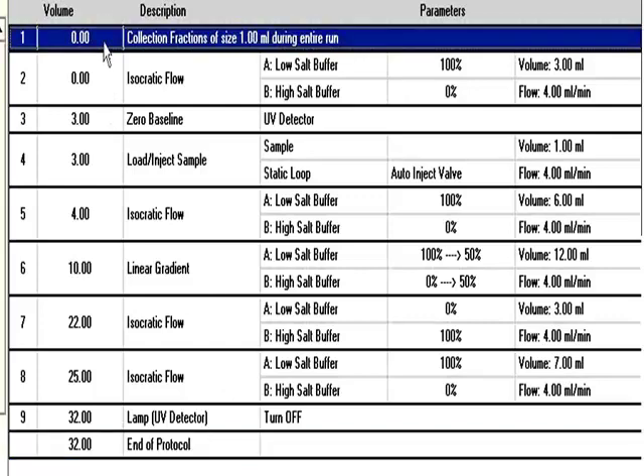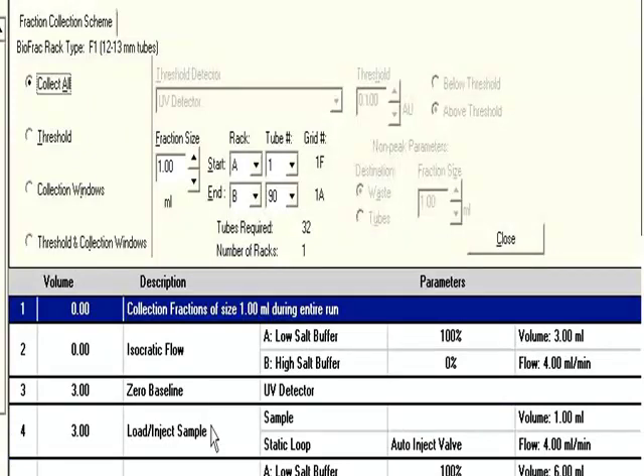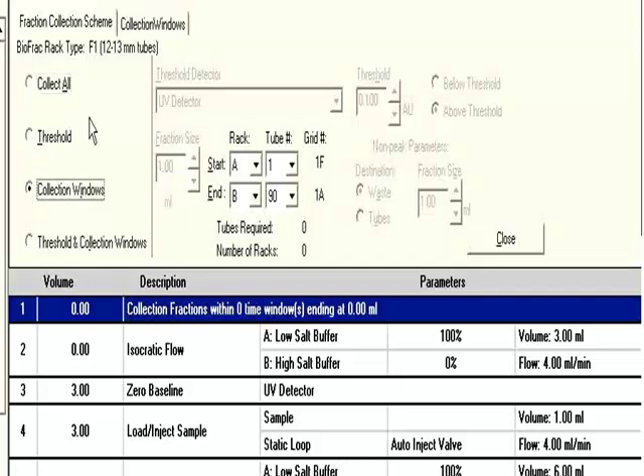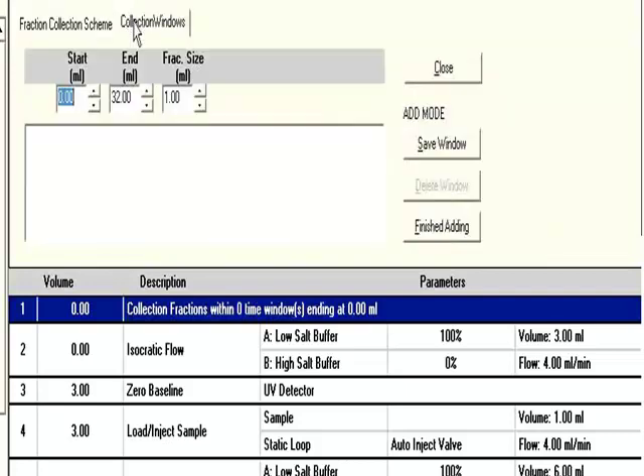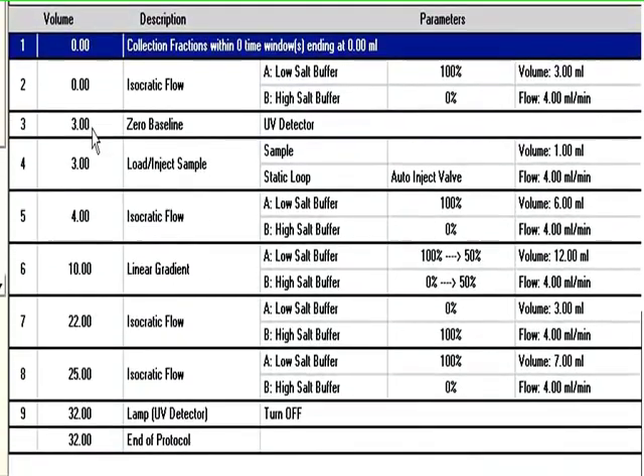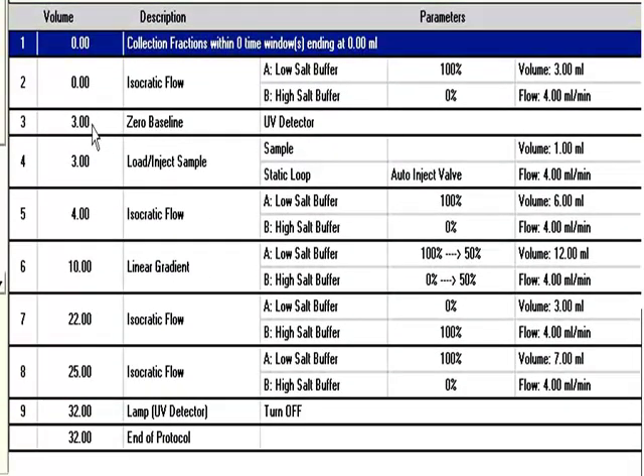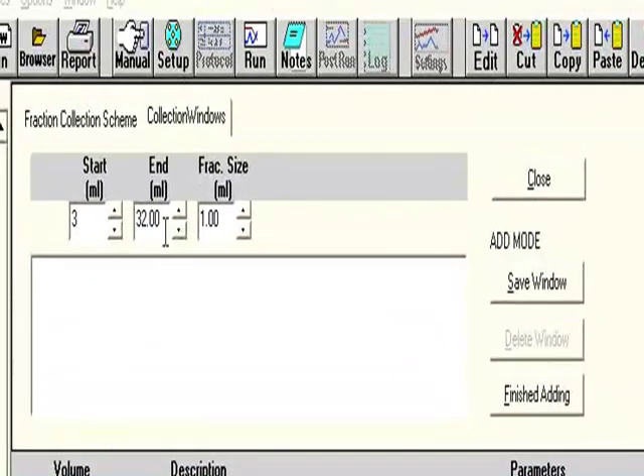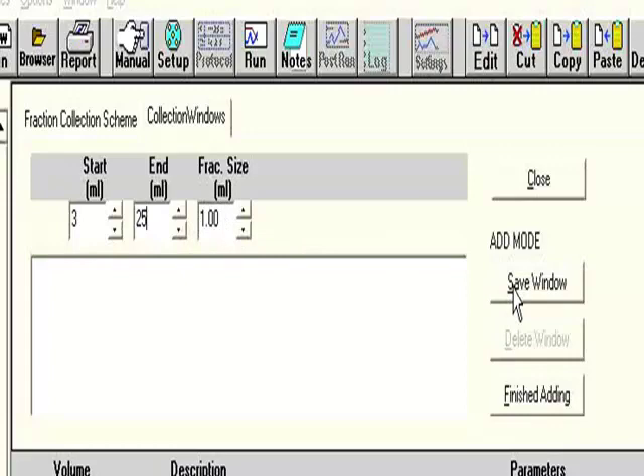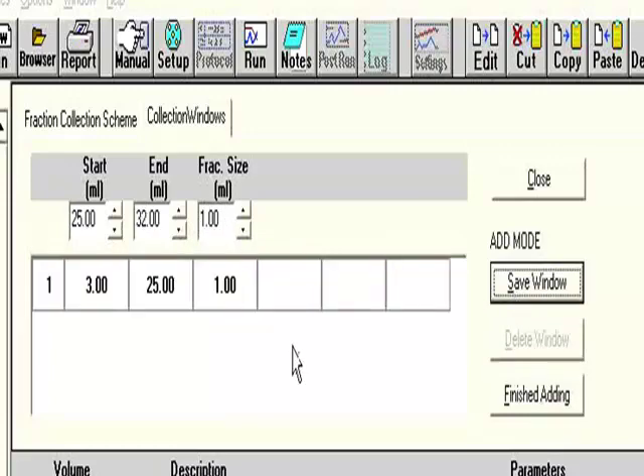Now we can go into the collect fractions. Double-click there, and you can see we have a variety of options we can use for collecting fractions. We can collect all the fractions, let's say 1 mL fractions from beginning to end. Or we can do collection windows, which is pretty nice. What we can do is we can set up different windows of collection in our protocols. We can say if I'm just equilibrating the system up to 3 mLs, I haven't even injected my sample yet once I get to the 3 mLs stage. I can say, let's start collecting at 3 mLs just when we start injecting our sample to catch everything that's going to come off the column. And by the time we've done our high salt, 100% of B, we're at 25 mLs by the end of this step here. So let's say we're all... Because everything's going to be off the column at that stage anyway. And we want to do 1 mL fractions so we can save this window. And we can say finish adding. You can add in multiple collection windows if you wish. So I can set up different collection windows. Finish adding. And we're good to go.